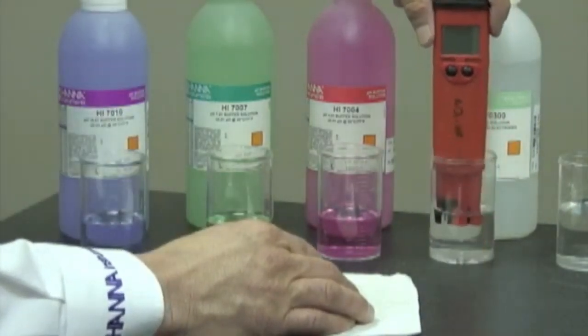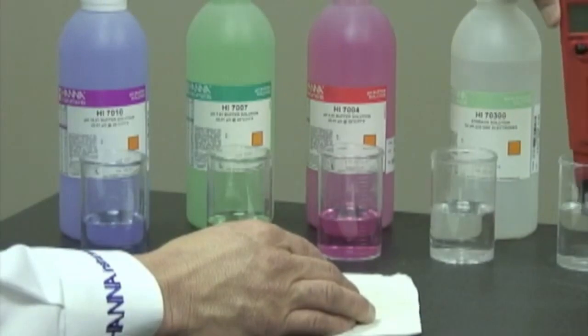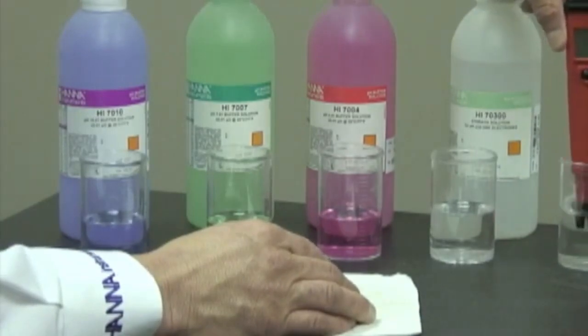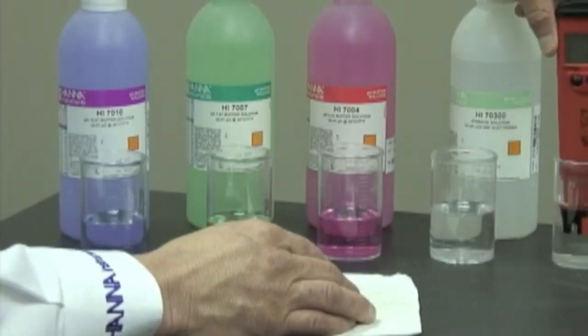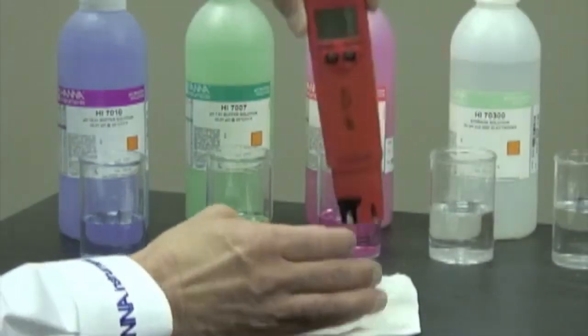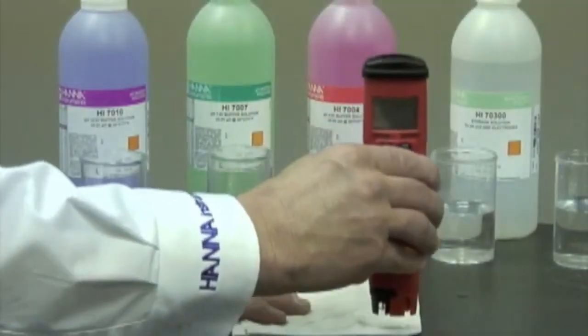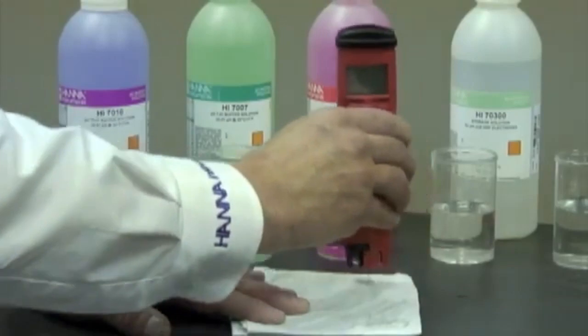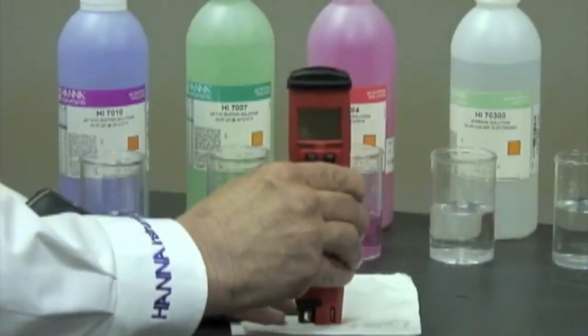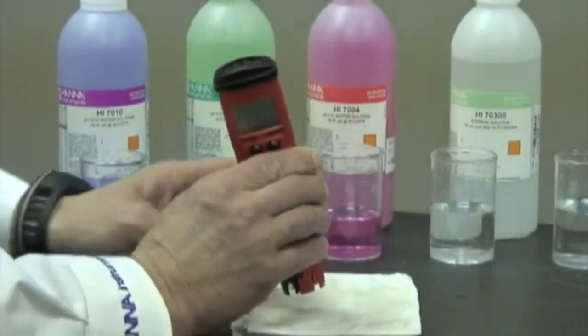I'm going to take the meter out of the storage solution, and I'm going to rinse it off in purified water. I'm going to get all the storage solution off of the electrode. Then what I like to do is blot it onto a paper towel to get any excess water off of the meter. Now we're ready to calibrate.